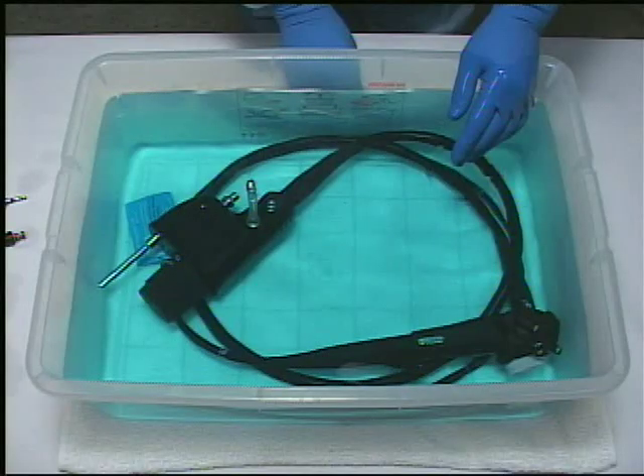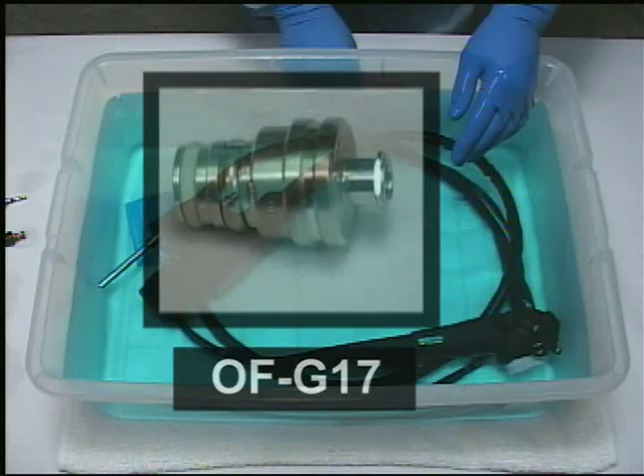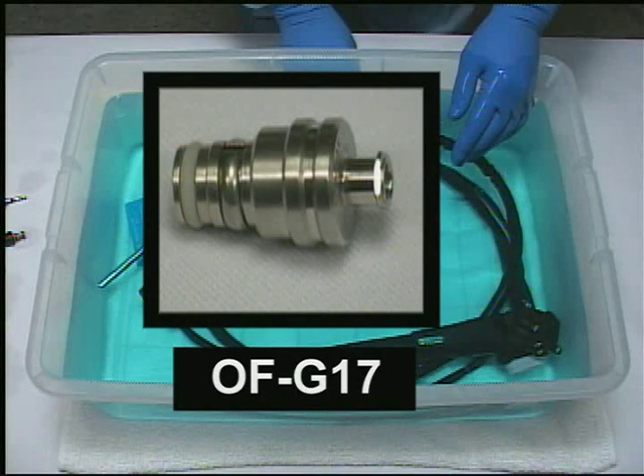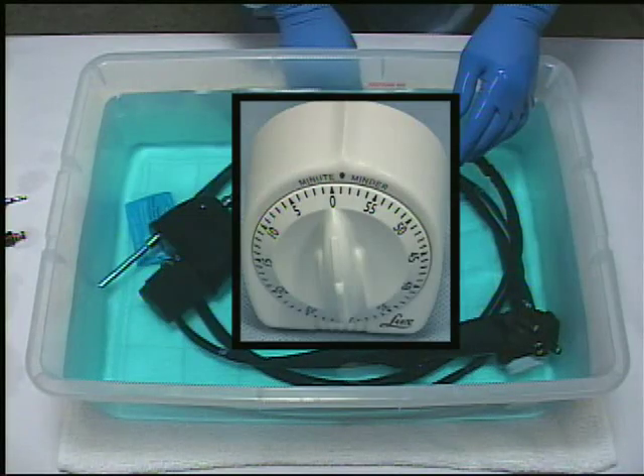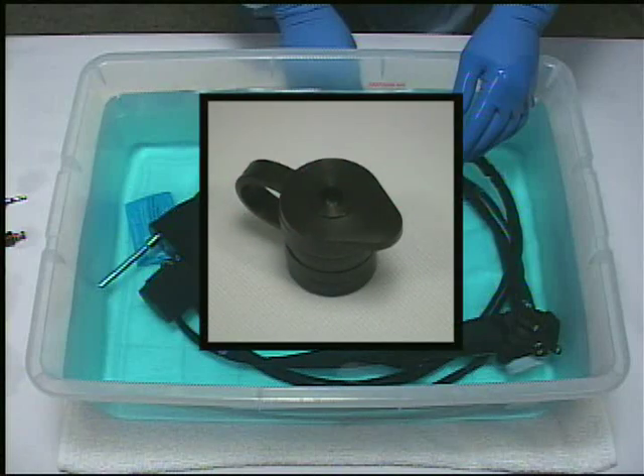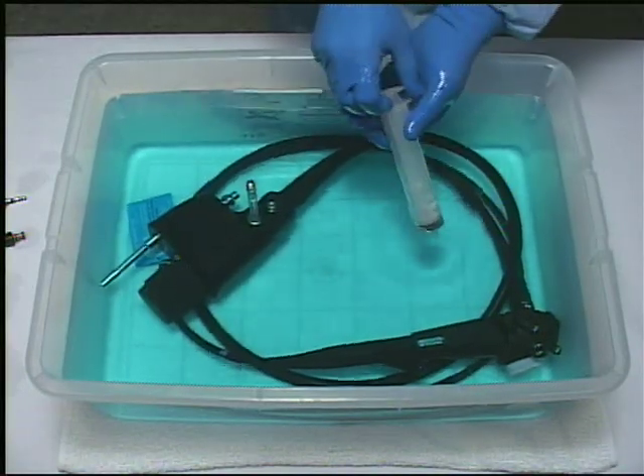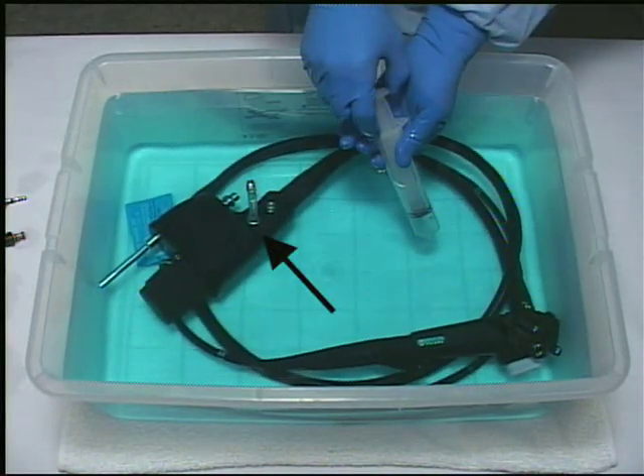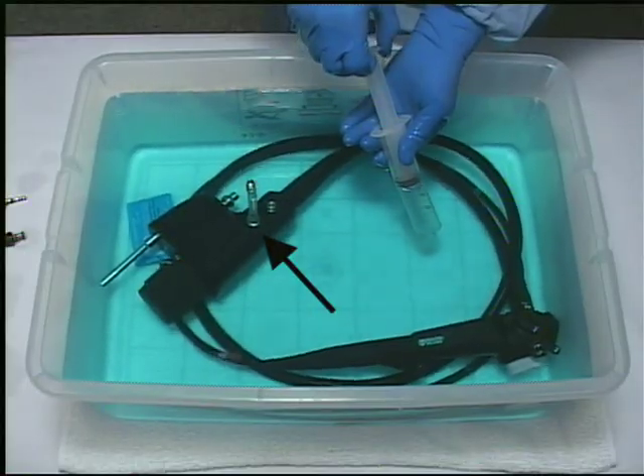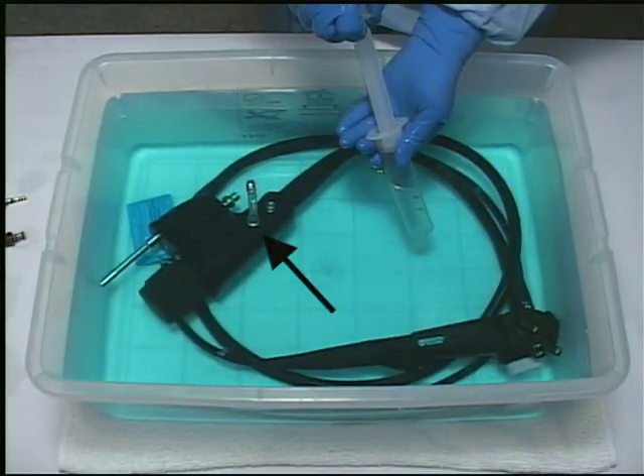After the entire scope is completely immersed and the air and water channels have been filled with disinfecting solution, model number OFG17 should be removed. Adhere to proper exposure times for the disinfectant. Confirm that a rubber inlet seal is already attached to the channel inlet for the next step. The suction channel cleaning adapter OEC8 must be attached to the suction nipple located on the PVE connector.